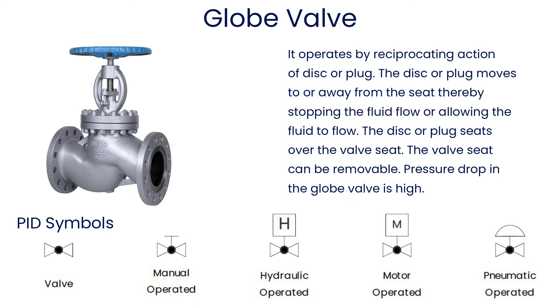Globe valve operates by reciprocating action of a disk or plug. The disk or plug moves to or away from the seat, thereby stopping the fluid flow or allowing the fluid to flow. The disk or plug seats over the valve seat, which can be removable. Pressure drop in the globe valve is high.